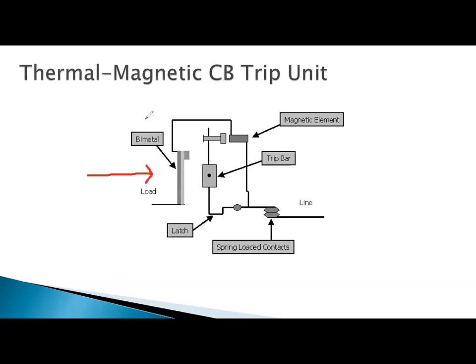And so this part, the bimetallic part, is for overloads. And so when too much current is flowing from our line side here up through this magnetic element over here to my bimetallic strip, it tends to bend that piece of metal. And when that piece of metal bends, it is going to hit what we call a trip bar.